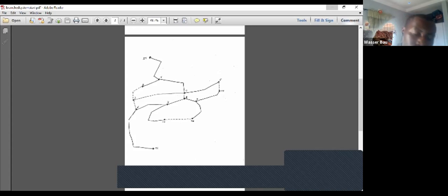So that is what I will expect even of us to do. So here now, if you finish, you run this, you click on this, you run your simulation. Now simulation says there are problems. And what are the problems? It told me that there are negative pressures. Negative pressure means there must be, okay, this new pipe that I included, I have not designed it. And maybe that's what is causing the negative pressure in the system.